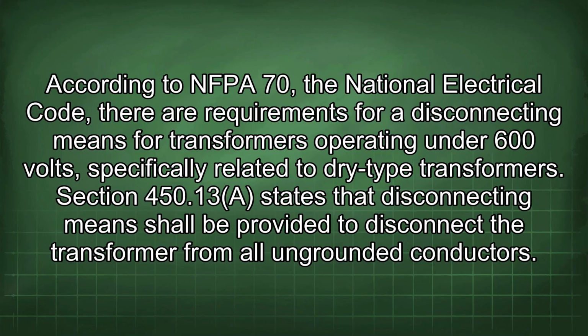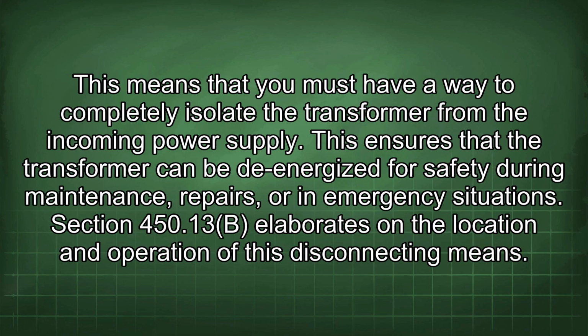According to NFPA 70, the National Electrical Code, there are requirements for disconnecting means for transformers operating under 600 volts, specifically related to dry-type transformers. Section 450.13 states that disconnecting means shall be provided to disconnect the transformer from all ungrounded conductors. This means that you must have a way to completely isolate the transformer from the incoming power supply. This ensures that the transformer can be de-energized for safety during maintenance, repairs, or in emergency situations.